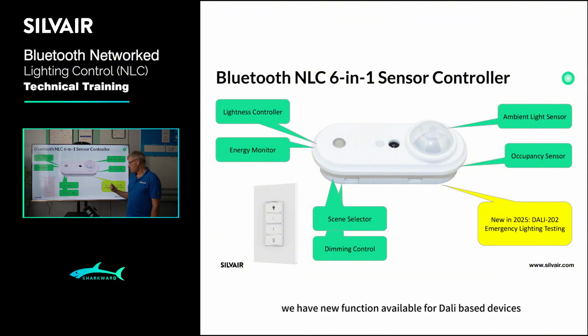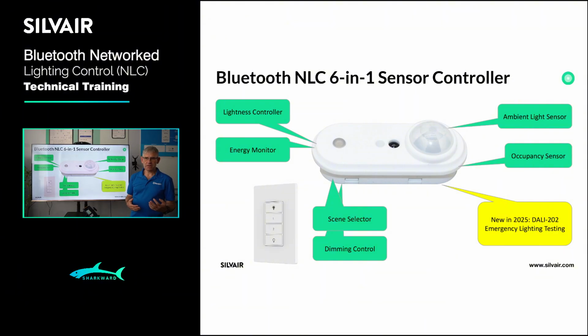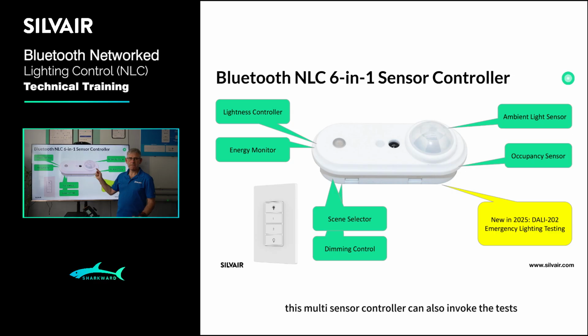We have a new function available for DALI-based devices starting this year, which is emergency lighting testing. The DALI standards define what's known as DALI Part 202, which defines how emergency lighting devices are tested. We have the functional test, and the duration test, also known as short and long test, or monthly and yearly test. Through DALI, this multi-sensor controller can also invoke the emergency lighting tests and report the test results.